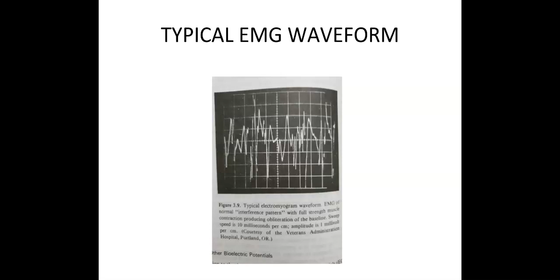Surface, needle and fine wire electrodes are all used for different types of EMG measurement. Surface electrodes are generally used where gross indications are suitable, but where localized measurement of specific muscles is required, needle or wire electrodes that penetrate the skin and contact the muscle to be measured are needed. As in neuronal firing measurement, both unipolar and bipolar measurements of EMG are used.